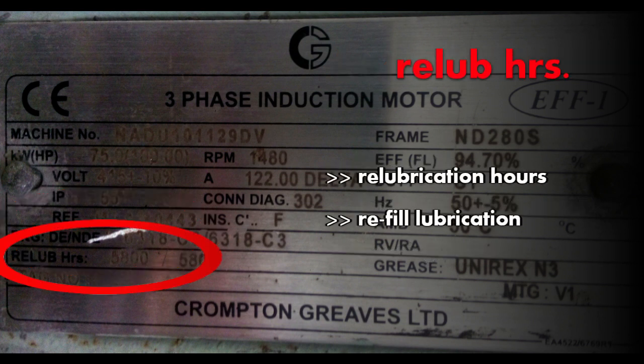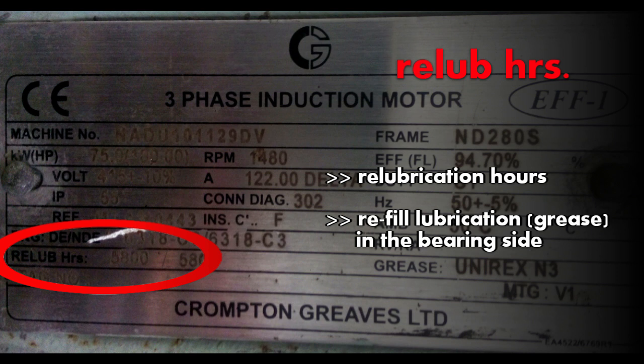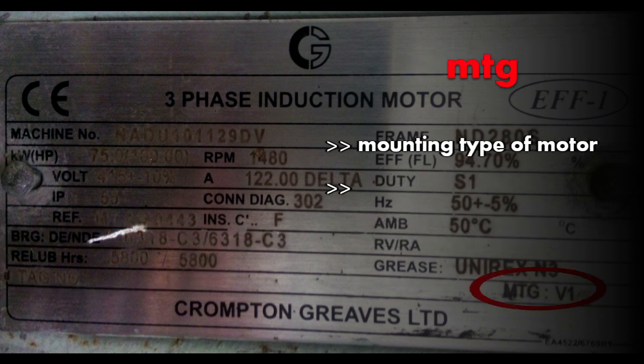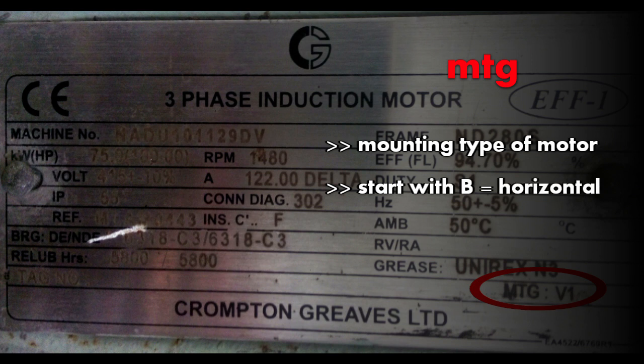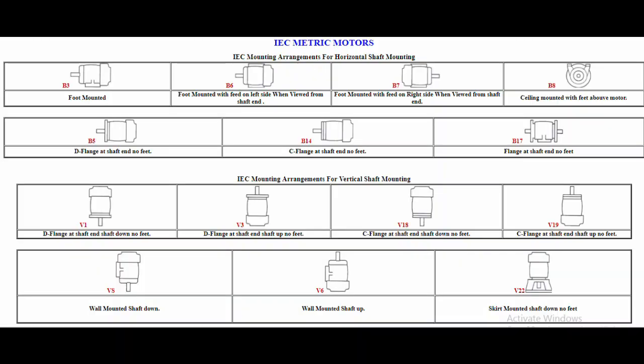Next comes the relube hours or relubrication hours. These are the number of hours after which you have to refill lubrication in the bearing side. It may be a grease. Next comes the MTG, that is mounting. It shows the mounting type of the motor. As you can see in the image, all the mounting types starting with B are the horizontal mounting, while the mounting starting with V are the vertical mountings.